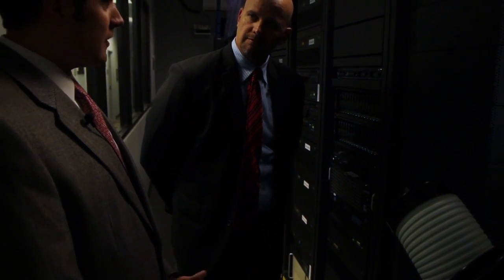And then the last thing you want this thing to do is, in the event of a complete power failure, hold you for enough time for your backup power supply to kick in. These things aren't wired to run for hours and hours. This should run for between 10 and 15 minutes so that it can hold the equipment until the generator can kick on and start servicing the primary power.